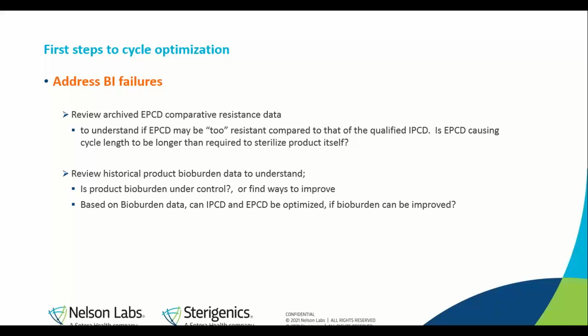So, for example, if the product bioburden back then is much different today, meaning that you've improved it, look into that, and that might give you an opportunity to improve on the design of the IPCD and EPCD, because you have much better control today of the bioburden, and that would be the first recommendation. And so you would always want to start there and see if there's room to work with in terms of reestablishing that EPCD so that it's more realistic to your products.